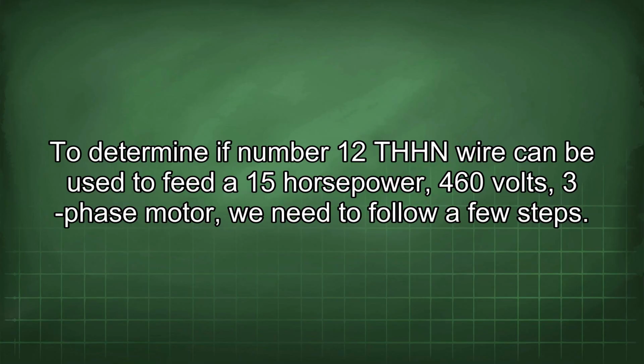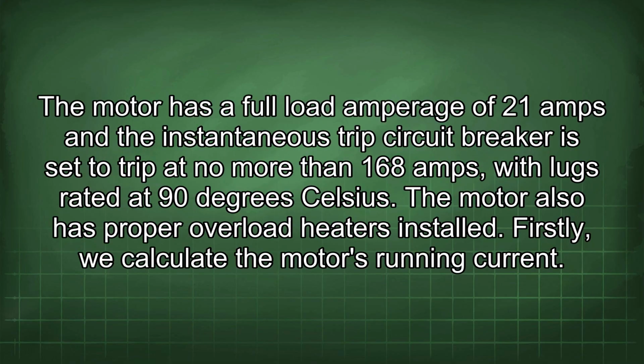To determine if number 12 THHN wire can be used to feed a 15 horsepower, 460 volts, three-phase motor, we need to follow a few steps. The motor has a full load amperage of 21 amps and the instantaneous trip circuit breaker is set to trip at no more than 168 amps, with lugs rated at 90 degrees Celsius. The motor also has proper overload heaters installed.